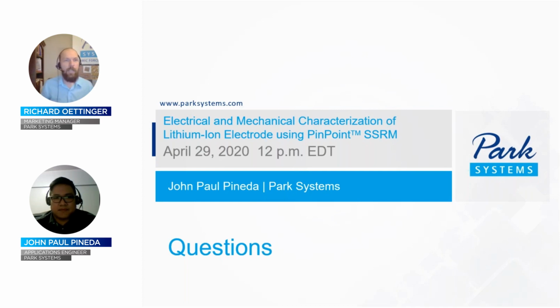First question is, what is the highest rate to image with Pinpoint? Okay, so first of all, thank you everyone for listening to my presentation. If you are referring to the scanning speed, it depends mainly on your settings. For example, if you set a high pixel size and low scan rate, the scanning will take longer. For the Pinpoint SSRM example I have shown to you, with pixel size about 250 by 150 pixels with a scan rate of about 0.22 hertz, it only took us less than 20 minutes to acquire the images.